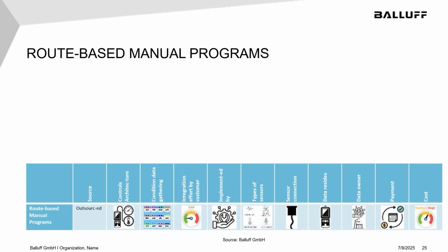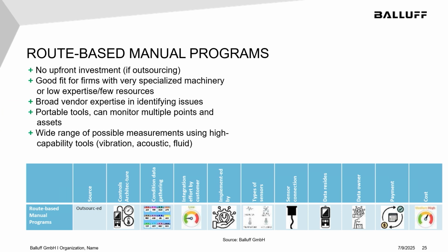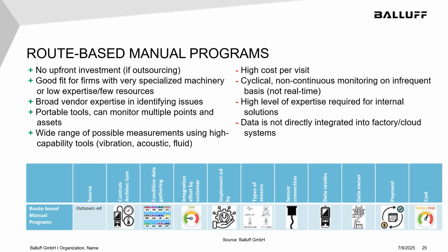This is where an outside company comes in every month, every quarter, and so on, often used for highly specialized equipment like power generation turbines, where you're looking at very precise measurements: ultrasound systems, high frequency vibration analysis, oil analysis, and so on. These often can only be done with very specialized, very expensive equipment that would not be cost effective to install permanently. So it's a very good approach for high value, high expense equipment where the vendor has very specialized knowledge about that equipment. But the challenge is it's often a high cost per visit, it's very cyclical, it's not real time, and so on.